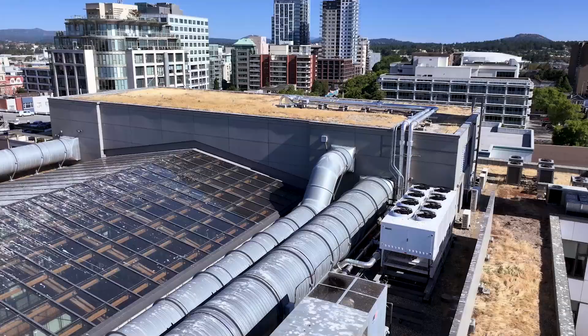The Atrium's original HVAC system is a VAV system with hydronic reheat coils. They are fed from a central air handler on the roof with cooling coils connected to a primary heat recovery system on the air side. The primary heating and cooling system is an air source heat pump with electric backup boilers. The original HVAC system performed fairly well in winter. However, in summer it struggled, especially on the hotter days of the year. We often found we had limited cooling capacity at the lower floors and a large number of tenant complaints due to solar load.